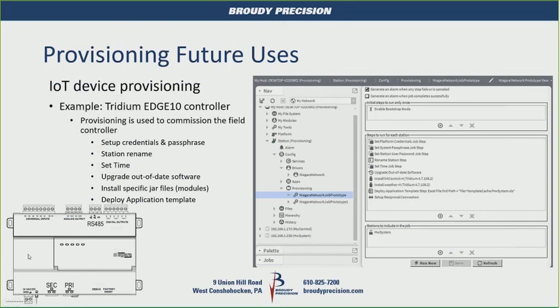has 5 universal inputs, 2 analog outputs, and 3 digital outputs. And then 2 Ethernet ports and a 485. A single 485. Yeah, the single 485 allows you to bring in, you can have it be BACnet MSTP for one device. You can have one IOR 32 or 34 device, only one, that can be on there as well, as extended I/O basically.